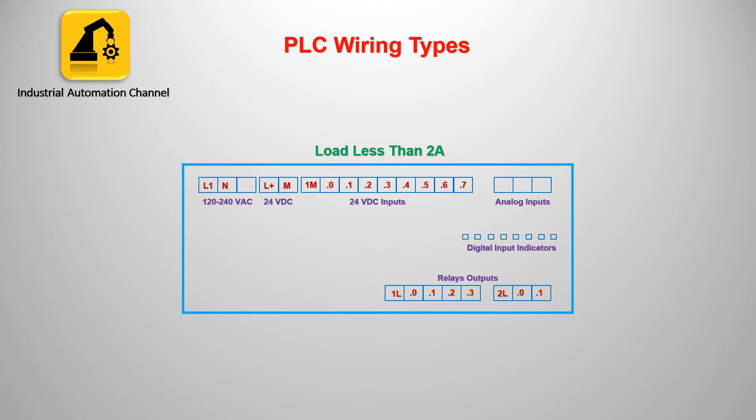Let's talk about output wiring types. For output, if our load draws less than 2A, then we can connect it to the PLC directly. If it draws more than 2A, we need to use an external relay rated for more than 2A. The output of the PLC energizes the relay coil and the contacts of the relay will change. We then connect our load with the desired voltage and ampere to the contacts of the external relay.